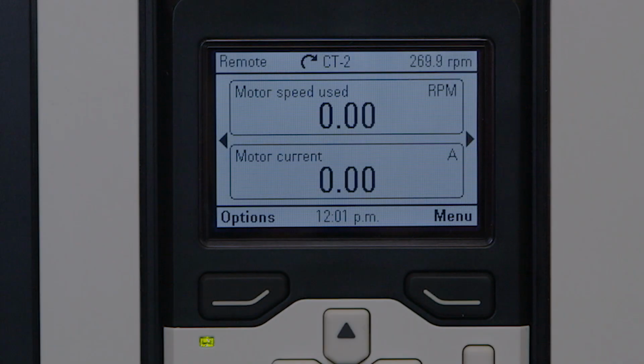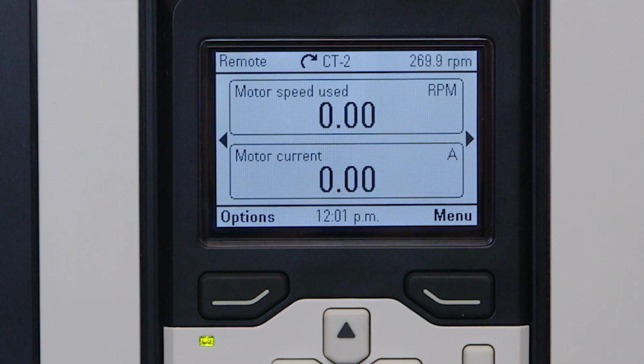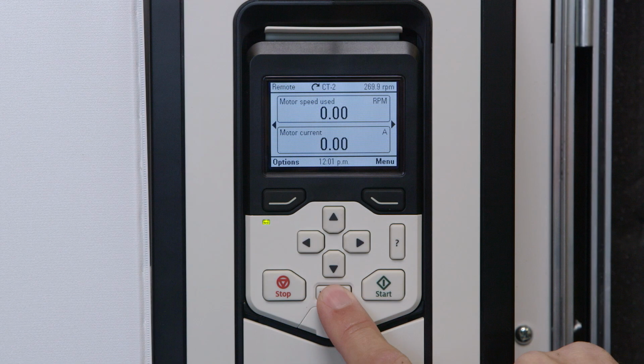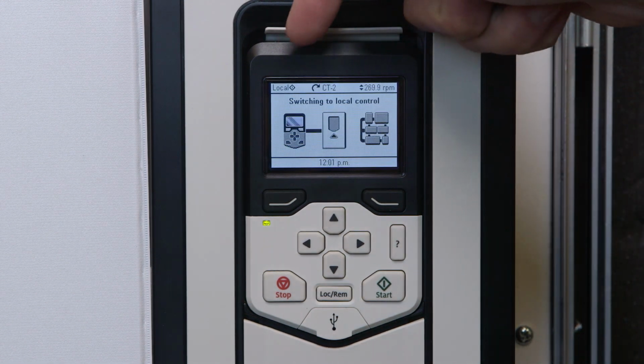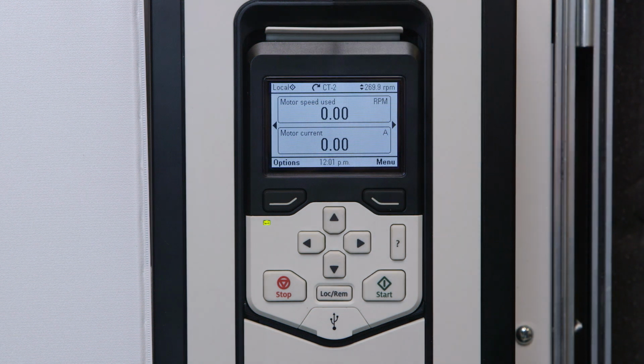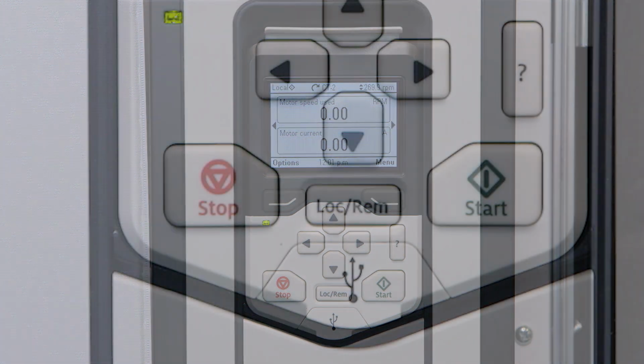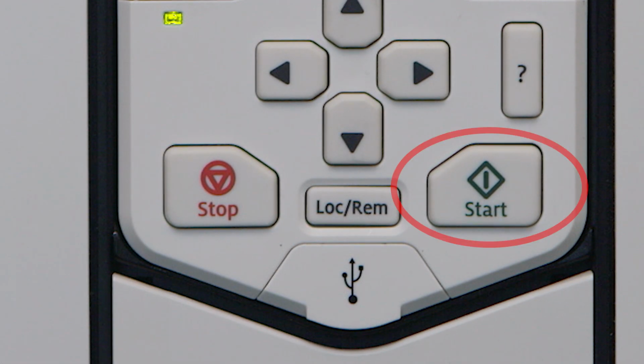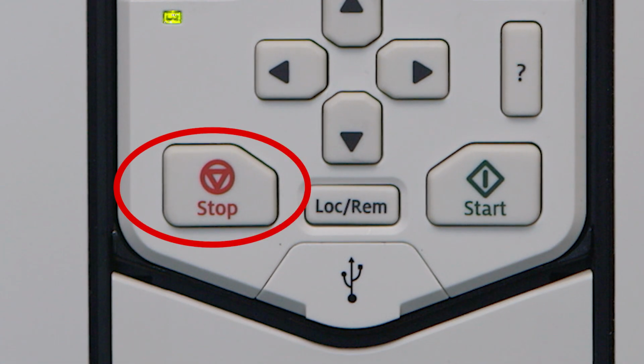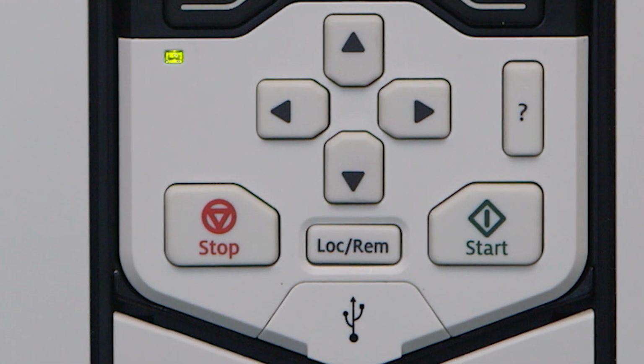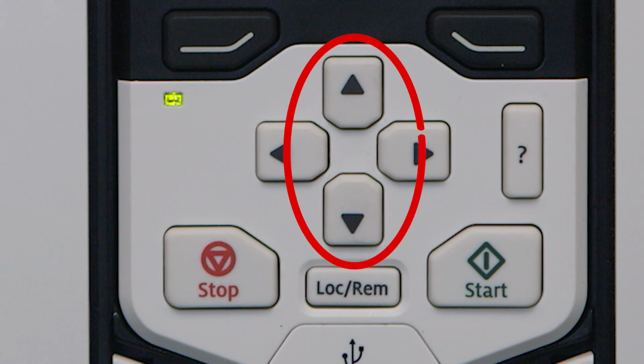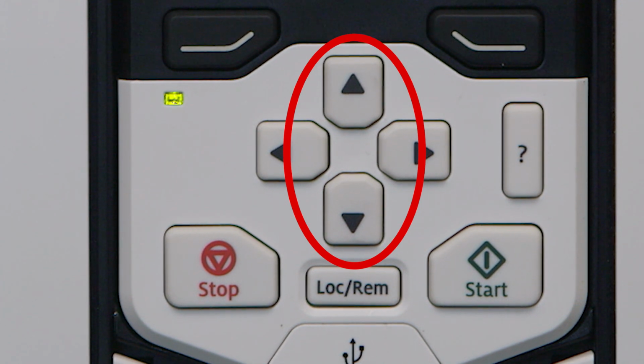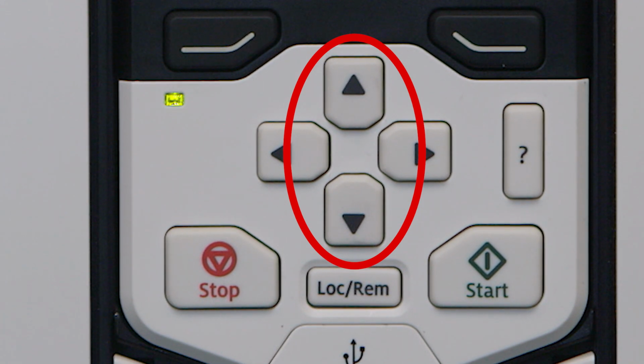To begin, let's test the system with the VFD and local control. Ensure the word Local appears on the screen. If the screen says Remote, press the Loc Rem button. The VFD is in local mode only if Local appears on the screen. The Start button starts the fan. The Stop button stops the fan. In local mode, increase fan speed by pressing up arrow and decrease fan speed by pressing down arrow.